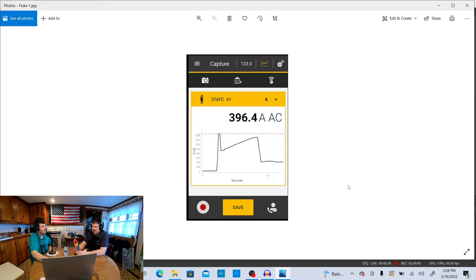A great way to do it: you can shut the power off, put the meter in place, close everything back up, turn the power on, and have it connected to your phone to watch what's going on. That's the soft start for that 350 horse motor. I shut all the power off, put the meter in place, connect to the phone, shut all the doors, turn the power back on, and let that motor rip while watching what it's doing.